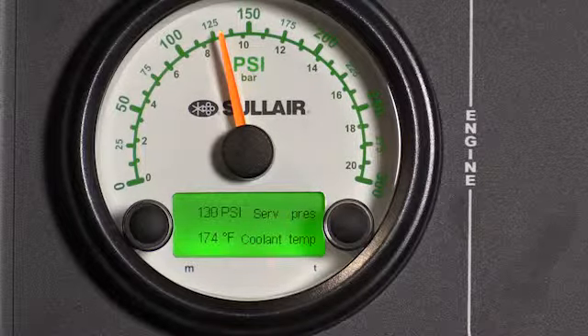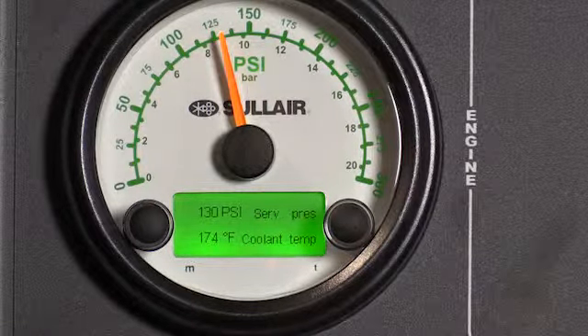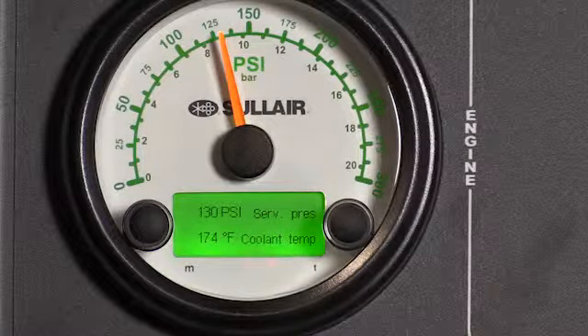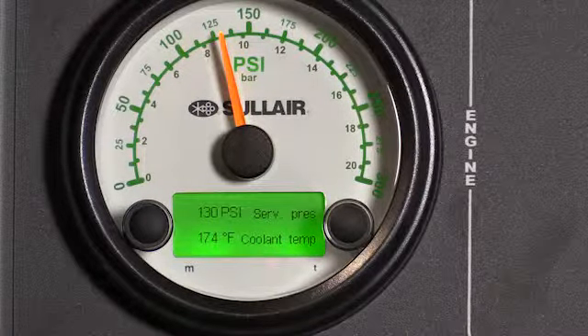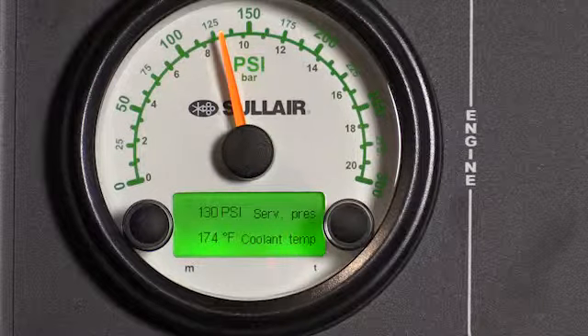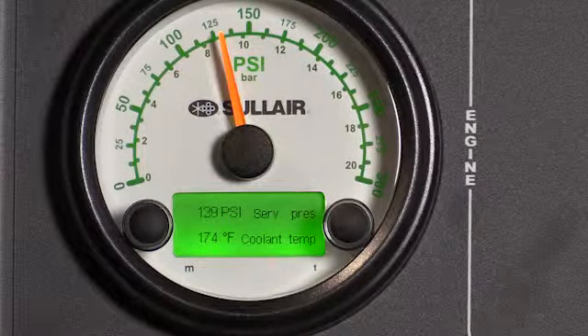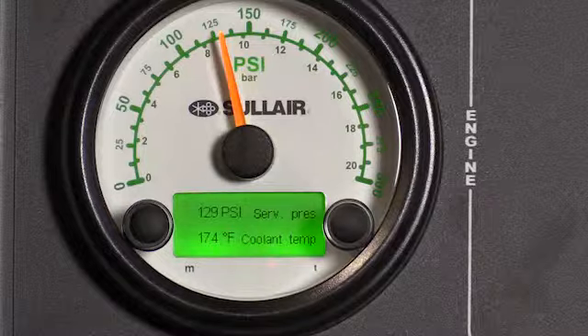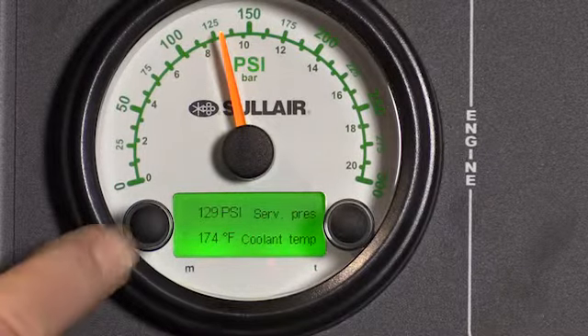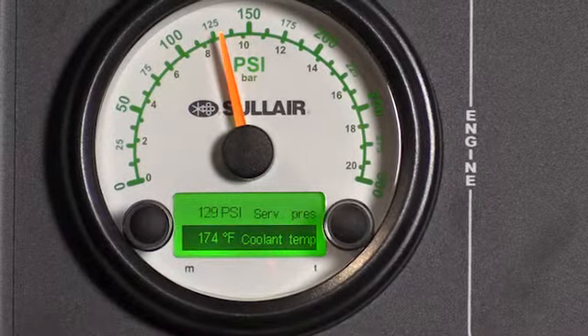Now that we're warmed up and we're in the run mode, providing service air, let's go ahead and scroll through some of the parameters that are available to us on the line 2 parameter. To display line 2 parameter, simply press the M button for a couple seconds. The line 2 parameter will be highlighted. Let's go through the different ones.